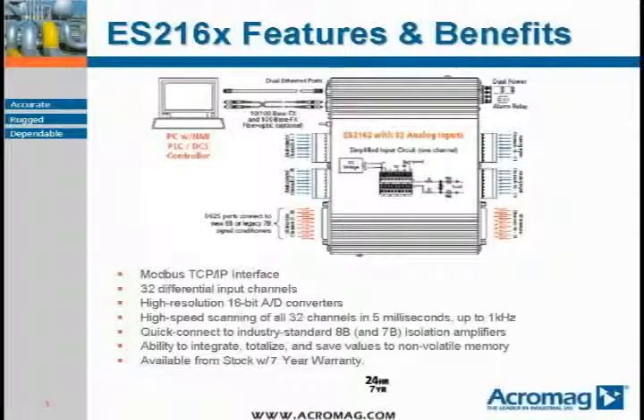The EtherStax ES2161 and 2162 models offer a lot of benefits. Each model supports Ethernet Modbus TCP/IP and UDP/IP protocols. They contain 32 differential current analog inputs for the 61 and high-level voltage analog inputs for the 62, which make these units suitable for any analog sensor applications in remote zones. The EtherStax also have high-resolution 16-bit A-to-D converters for accurate conversion of precision measurements.